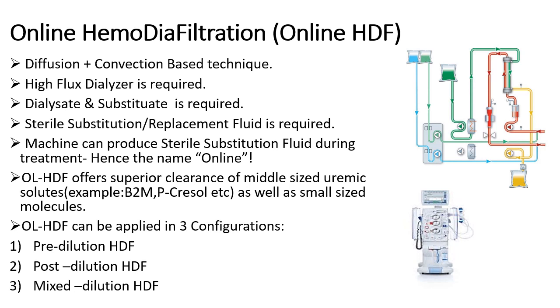Online haemodiafiltration can be applied in three separate configurations: pre-dilution, post-dilution, or mixed dilution. In pre-dilution, the substitution fluid is administered just before the dialyser. In post-dilution HDF, the substitution fluid is administered after the dialyser. In mixed dilution, the substitution fluid is simultaneously administered both as pre-dilution and as post-dilution.